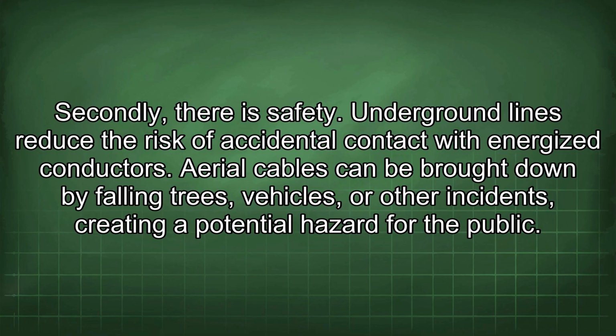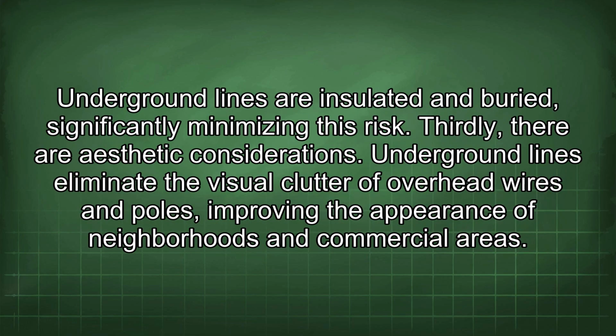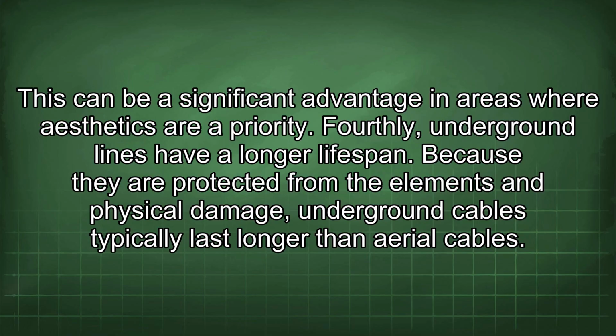Secondly, there is safety. Underground lines reduce the risk of accidental contact with energized conductors. Aerial cables can be brought down by falling trees, vehicles, or other incidents, creating a potential hazard for the public. Underground lines are insulated and buried, significantly minimizing this risk. Thirdly, there are aesthetic considerations. Underground lines eliminate the visual clutter of overhead wires and poles, improving the appearance of neighborhoods and commercial areas. This can be a significant advantage in areas where aesthetics are a priority.